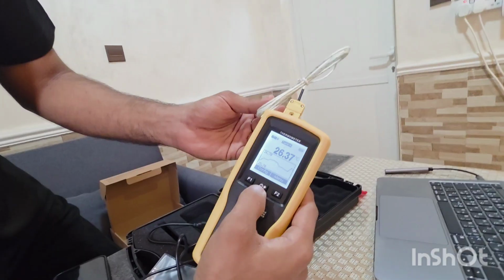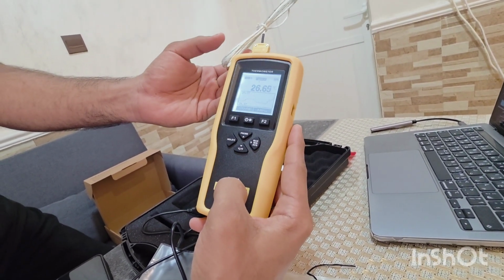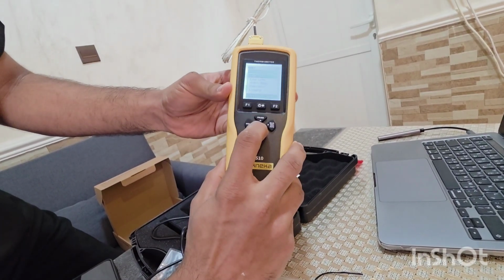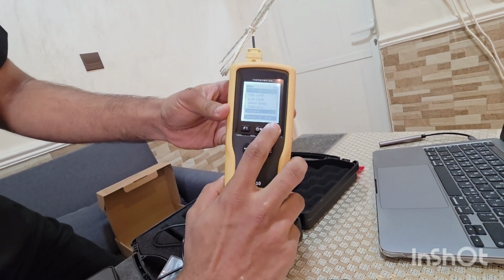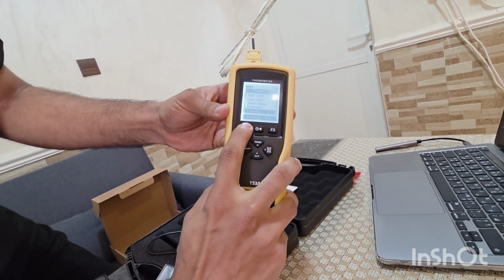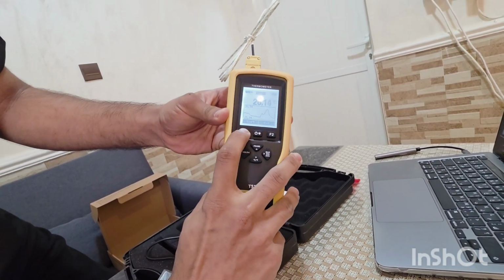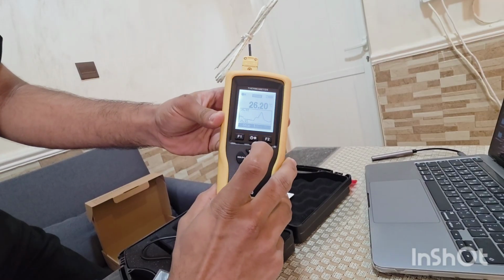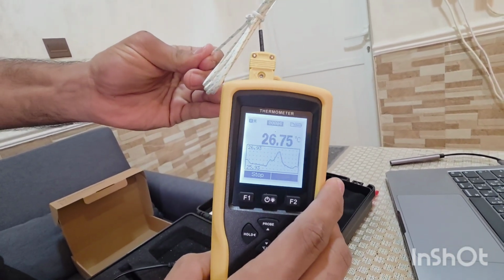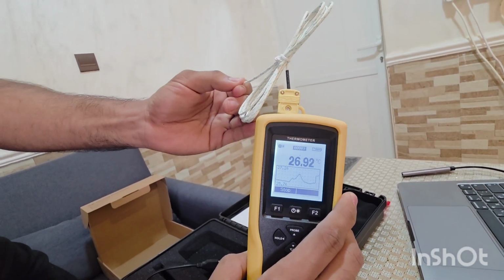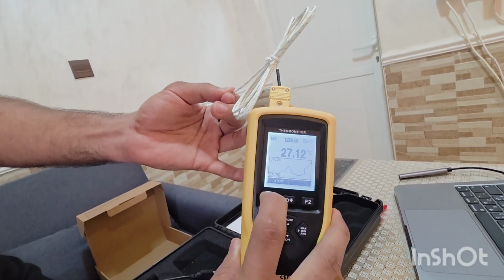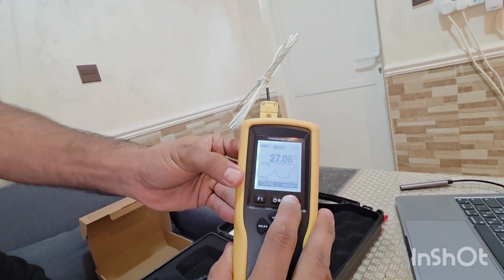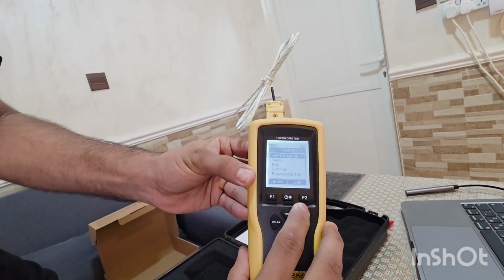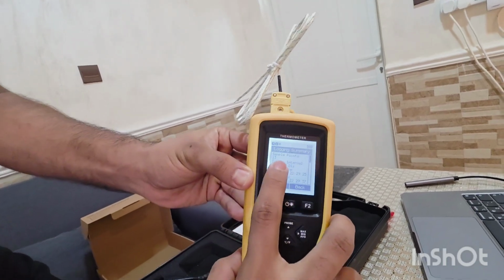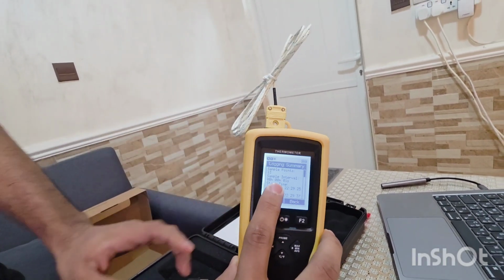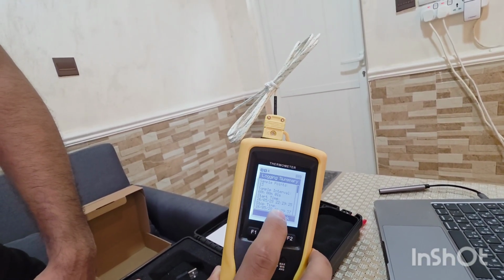I'll show you how to record the data, which is very important for a temperature data logger. Go to menu; the low limit and high limit can be set based on your requirement. For logging, go inside logging, enter, start logging. After that you need to press F1 again to start, and now it is logging. After some time we stopped logging, so one file is created. To view the file, go to menu, logging, enter, view the logged file, view. I kept logging for only 13 seconds, so there are 13 sample points. The sample interval is 1 second by default. Start time, stop time, everything it will show.